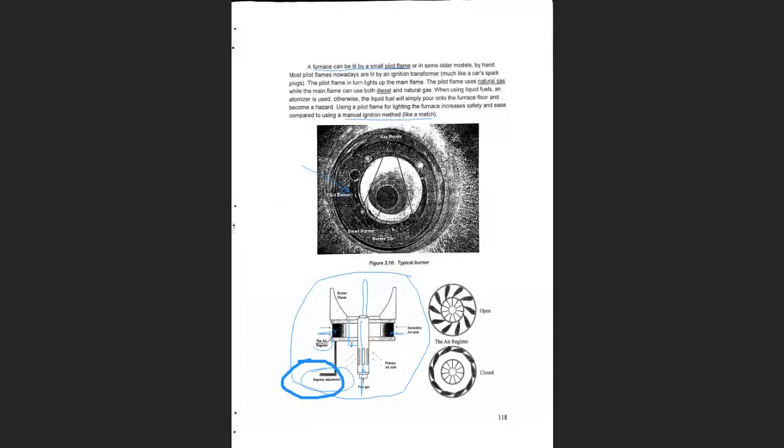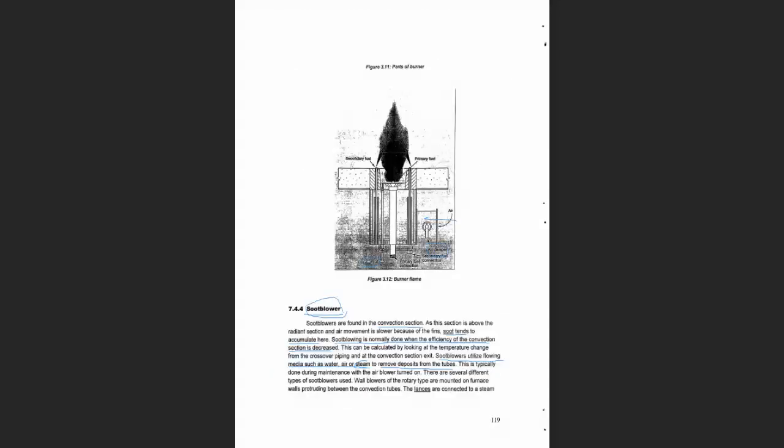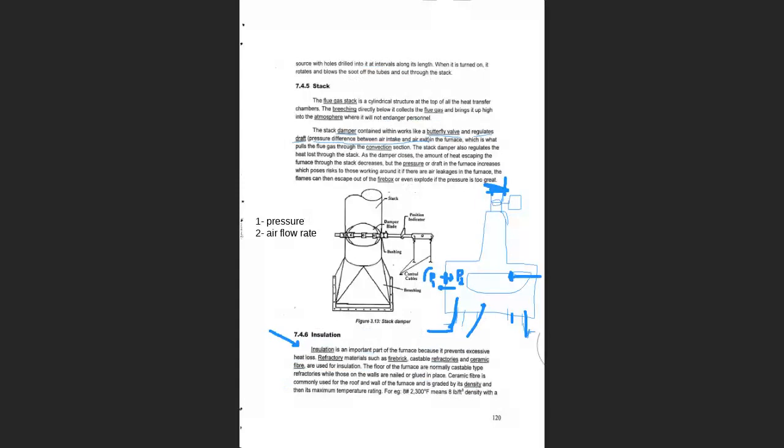وفي نفس الوقت من خلال الكنترول روم يتم التحكم في الدامبر هذا، الإير دامبر. جميل. طبعا الإير دامبر يكون موجود إذا كان عندك suction fan أو ID fan، يعني induced draft fan. فعملية متعبة نوعا ما في هذا النوع من الأفران، إنه عندك manual valves. يعني تخيل لو كان عندك 64 بيرنر تحتاج إنك تشيك عليهم واحد واحد، عملية متعبة نوعا ما.